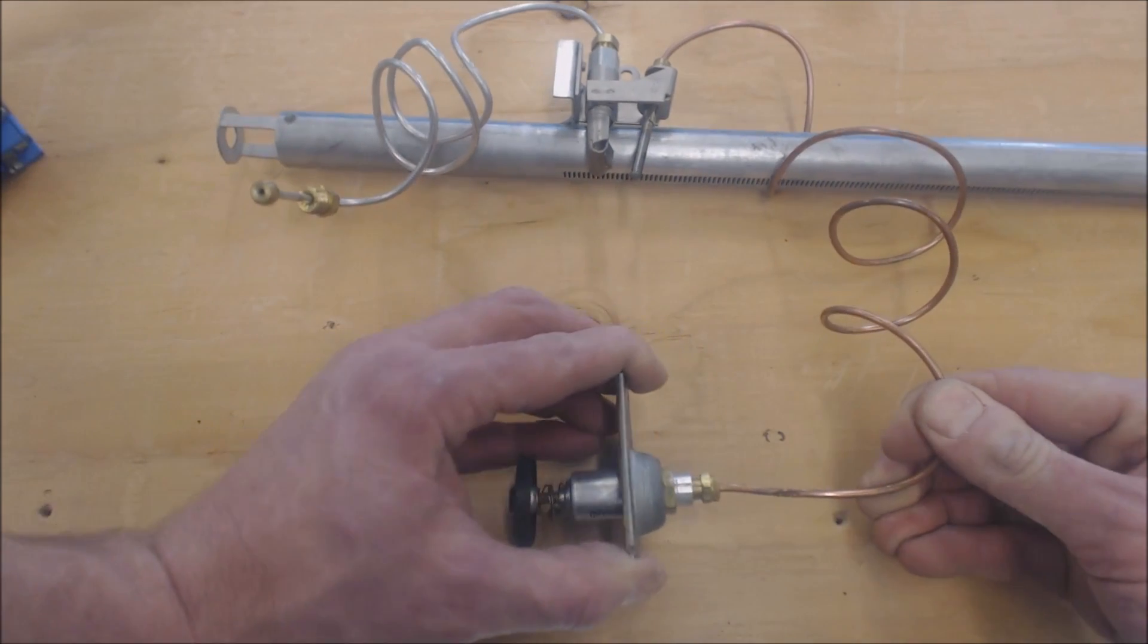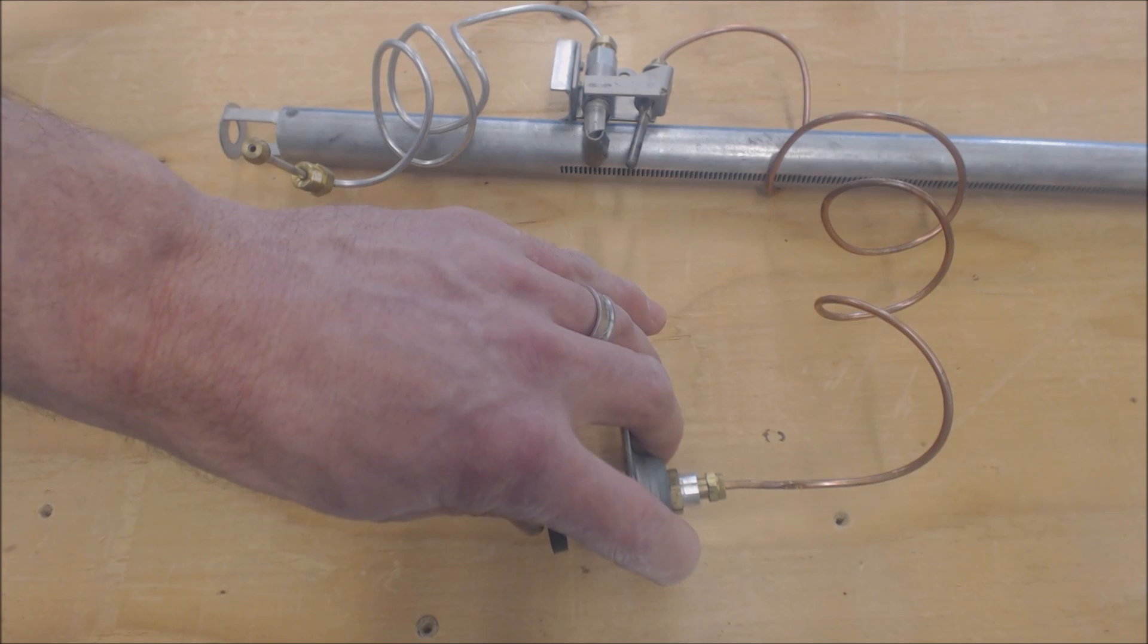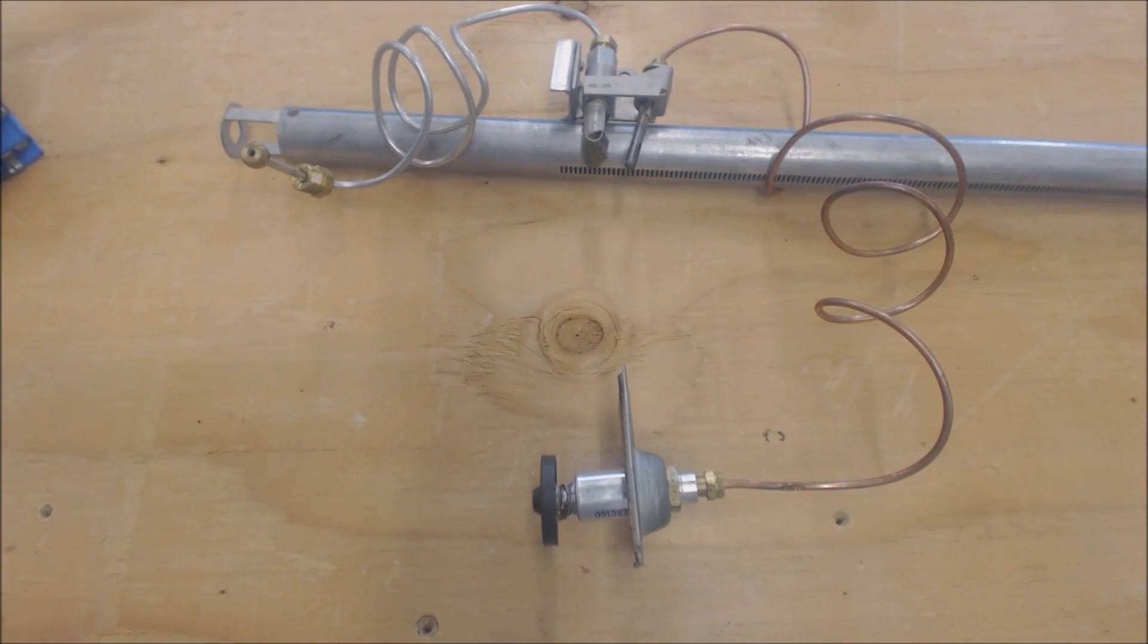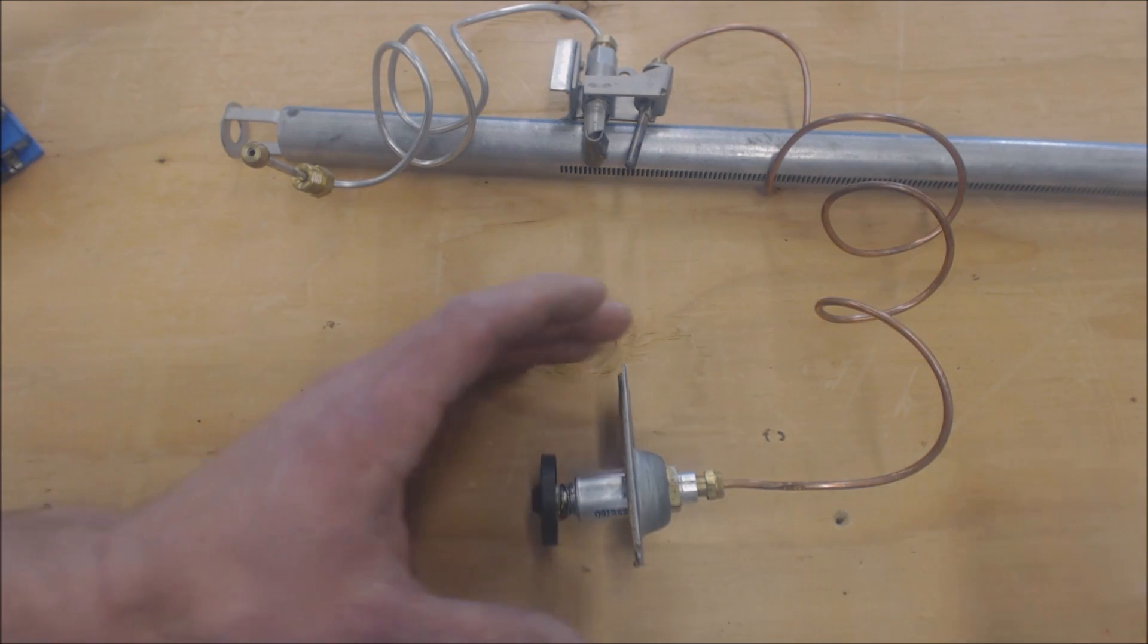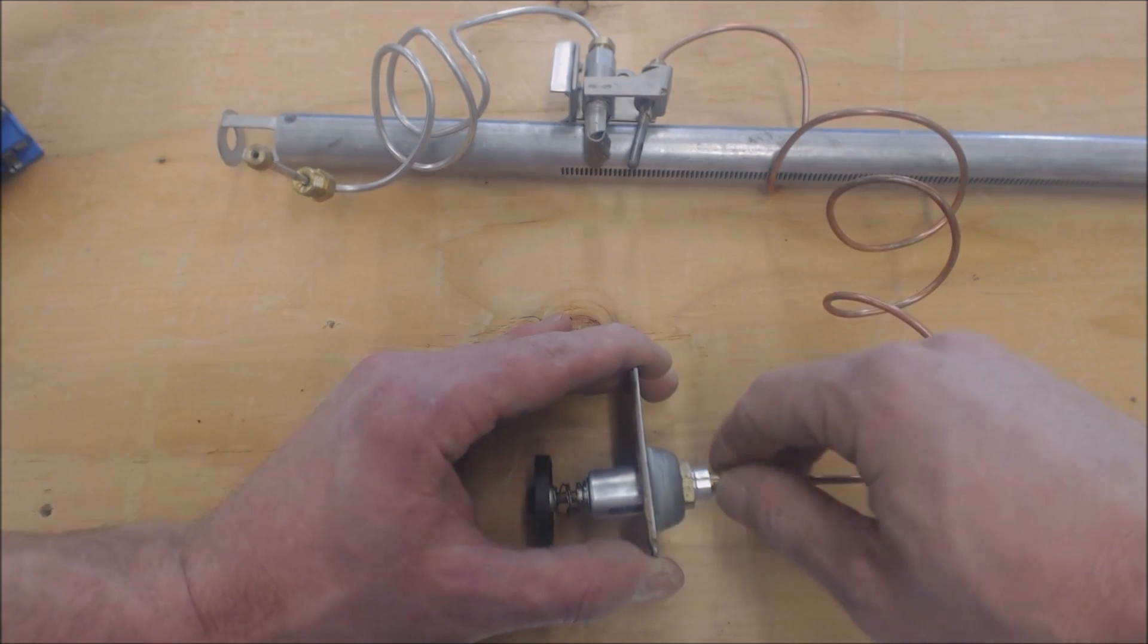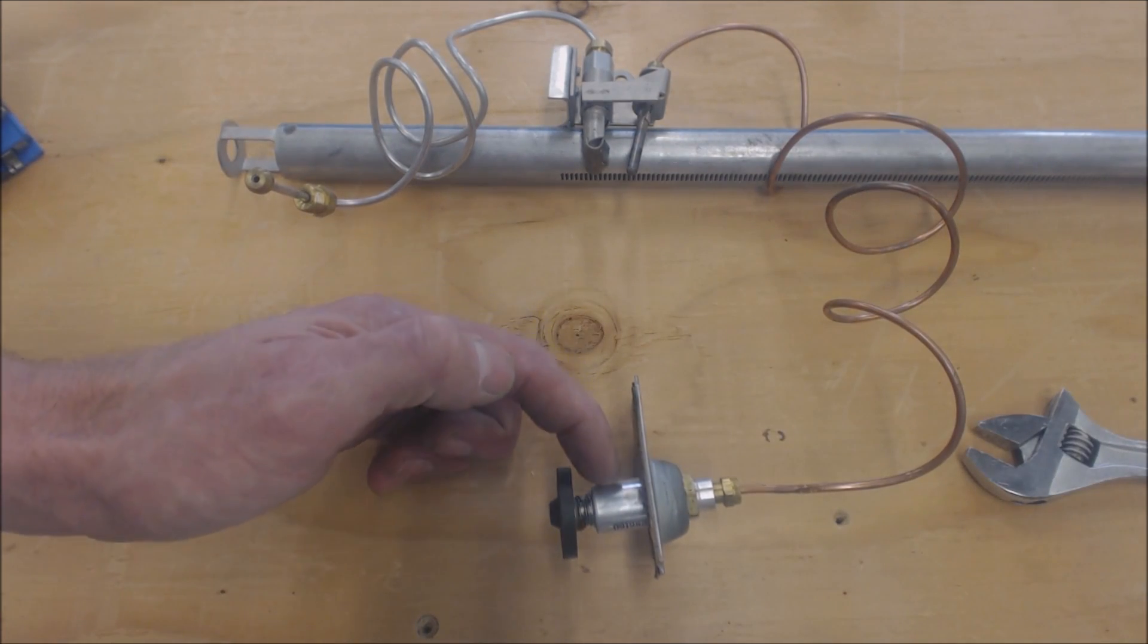We're going to do the same thing again, but this time I'm going to disconnect it here. Now it's holding it again and we're going to disconnect it. You see that? We just loosened it. Let's tighten it again, hold it in, and see how it holds. That's the function of this solenoid along with the thermocouple.